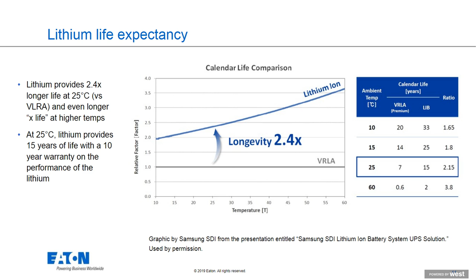Keep in mind lithium batteries, just like valve-regulated ones, are somewhat affected by temperature. The higher the temperature, the less service life you get from either chemistry. At the optimum point, typically 25°C or 77°F, valve-regulated lead-acid has a 5-year life and lithium has a 10-year life. Looking at 40°C, or 104°F, the valve-regulated lead-acid battery won't last 5 years—more like 2.5 years. The lithium battery is 3 times that, but that works out to around 6 years, not 10. So the higher the temperature, the more the lifetime is affected for either chemistry.